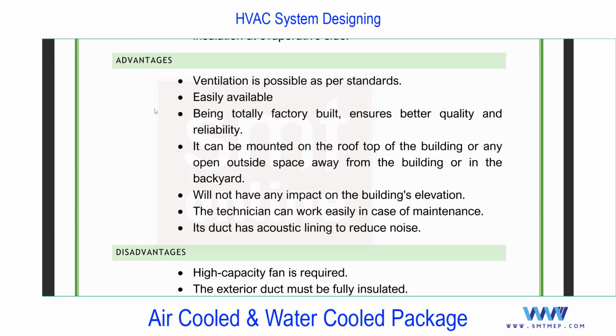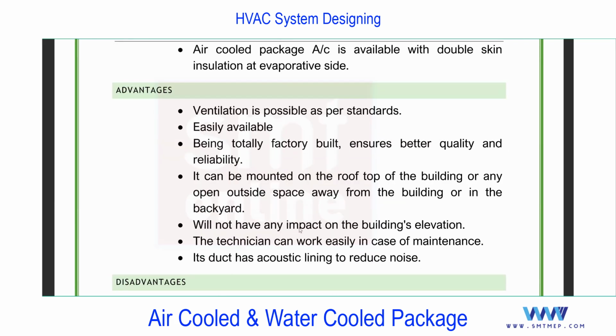Again, this point is related to the air cooled. In water cooled side, again, the cooling tower side, we need to go for installation. But still, in that case also, we are not disturbing the refrigerant cycle, and it can be placed on the rooftop or any open space away from the building or backyard. Rooftop means, again, I'm talking about air cooled package. We are not placing the water cooled package on the rooftop. Water cooled package we are placing inside the building, except the cooling tower.